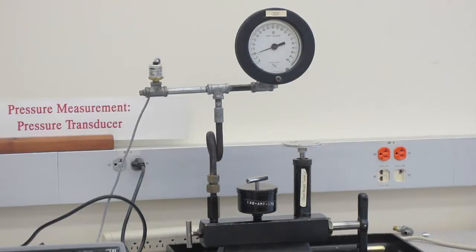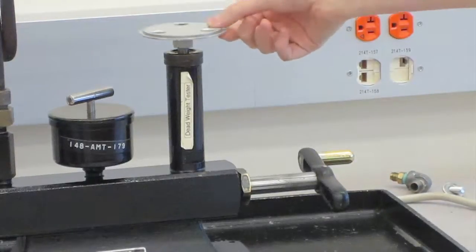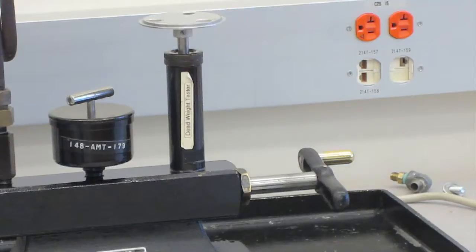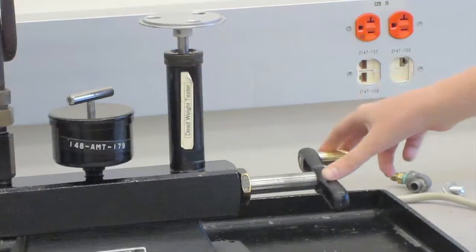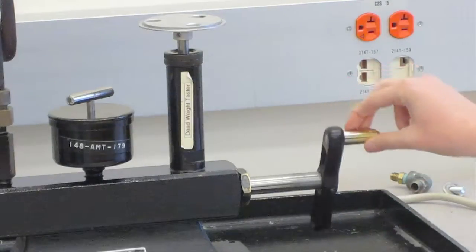You can see that the platform is in equilibrium position between the top and the bottom of its travel. If the weight platform moves to the extreme bottom or the top of its travel, then you need to slowly adjust the hand wheel until it is in the equilibrium position.